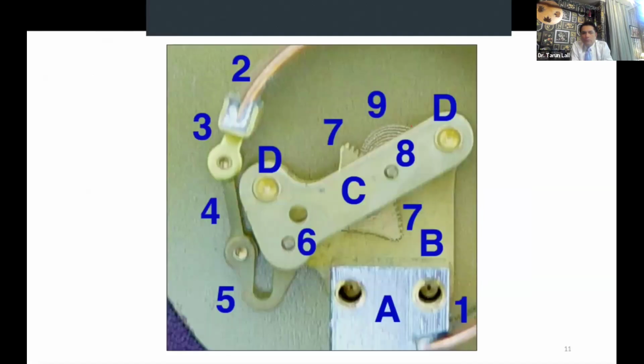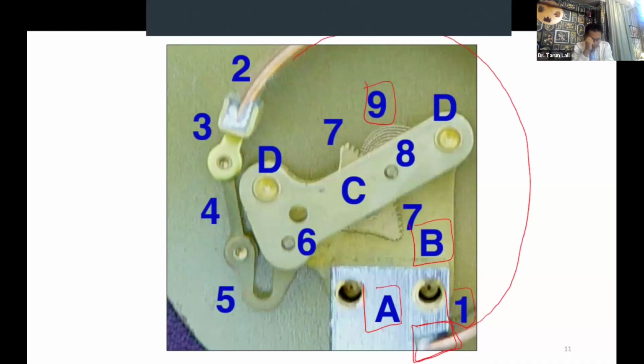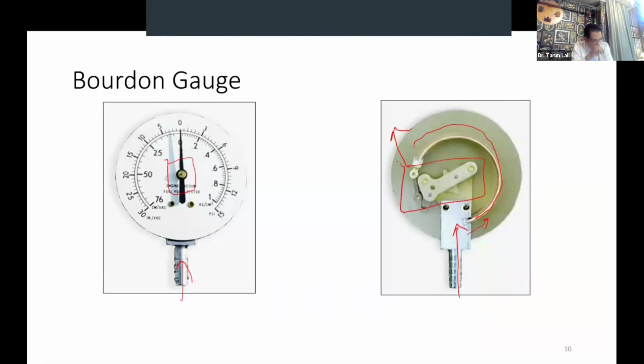Now if we see all these nomenclature on this, the A, B, C, D are the fixed parts of the Bourdon gauge when seen from behind, and all these numbers 1 to 9 are the moving parts. So you can see that as the pressure has come from this end, gone through that curved tube, and come here, it has caused this tube to move. And you can see that through this 4, 5, 6, 7, 8, and on the other side of this machine is the needle. All this mechanism is connected to this needle, and as this moves, the needle moves and it shows you the correct pressure. So that is how the Bourdon gauge works.